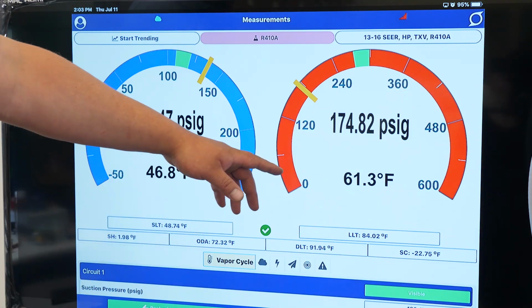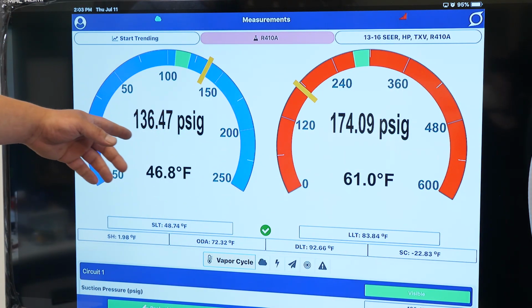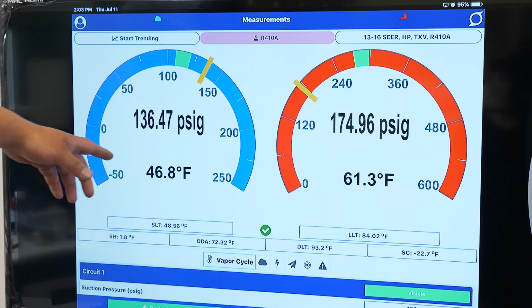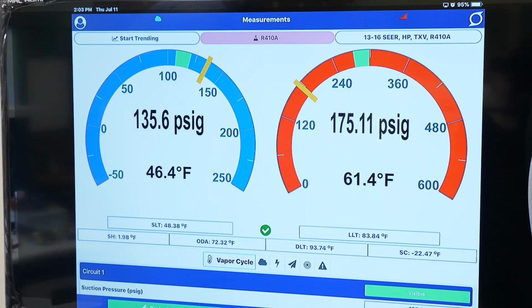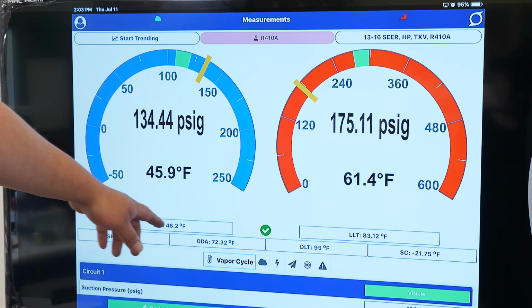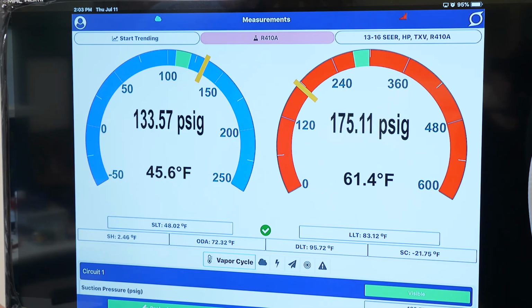So as you can see, our high pressure is starting to increase, our low pressure is starting to decrease. Our coil temperatures are starting to get down and up to where we need them to be. You can see our four temperatures, our suction line temperature, outdoor air, discharge line temperature, and liquid line temperature. Our superheat and our subcooling, both of those will start to stabilize here in about 10 minutes.